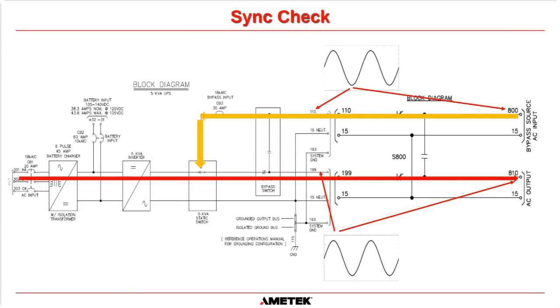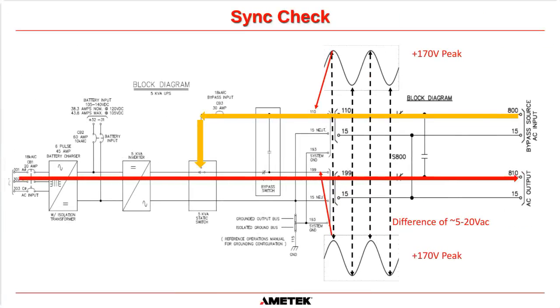So what we're saying here is our bypass source is coming in here, and it goes into our UPS at this point here. So wire 110 is our bypass supply, and wire 199 is the output from our inverter. Okay, and you can see we've got our waveform here and our waveform here, and you'll see on the next page that they are in phase with each other through these dotted lines, the peaks and the troughs are completely in phase with each other.